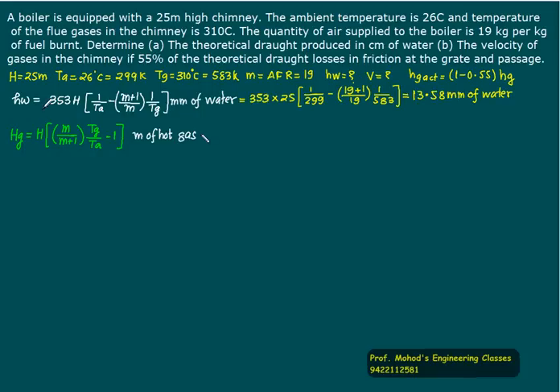If I use the equation of hw: 353 × height of chimney 25 × [(1/Ta) - ((m+1)/m) × (1/Tg)], where Ta is 299K, m is 19, and Tg is 583K. Solving this, we get 13.58 mm of water. If you want cm, then it equals 1.358 centimeters of water.